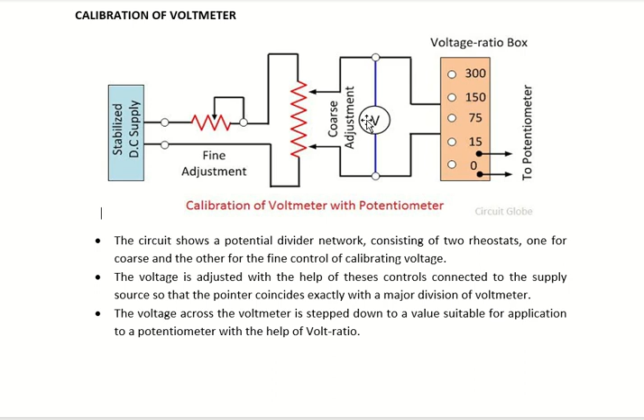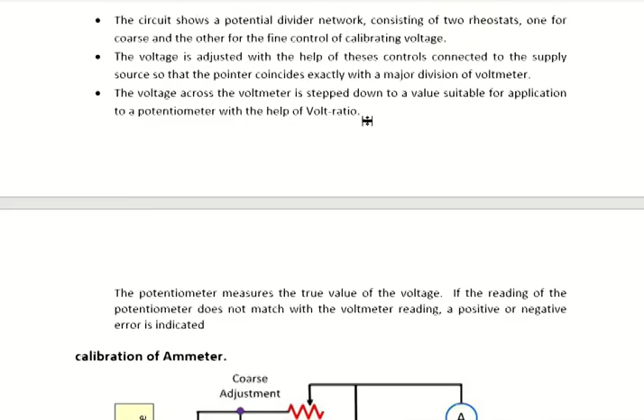Next you connect the voltmeter and check whether the voltage calculated from the potentiometer and the voltmeter reading are the same. If both readings are the same, the voltmeter is calibrated; otherwise there is an error. This is the calibration of voltmeter.